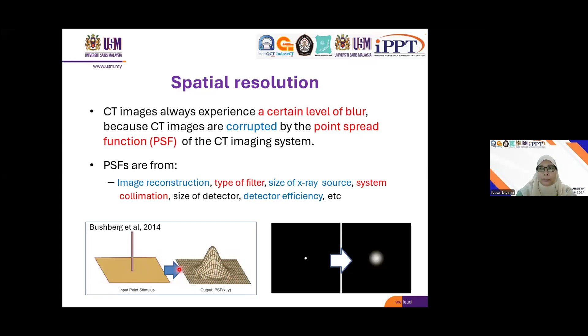So what is spatial resolution? In certain textbooks they use different terms to describe spatial resolution. Sometimes they use high contrast resolution, sometimes they use the term detail resolution. But all of these terms describe spatial resolution. Spatial resolution is the ability of the CT scanner to resolve two objects that are close to each other. If you have two objects or pathologies that are near to each other, your CT scanner should be able to separate them as two objects. Usually it is described as the visible sharpness of fine borders or edges of a structure. Spatial resolution is determined using the point spread function, line spread function, modulation transfer function, and also the edge response function, ERF. These are all the parameters used to represent spatial resolution.